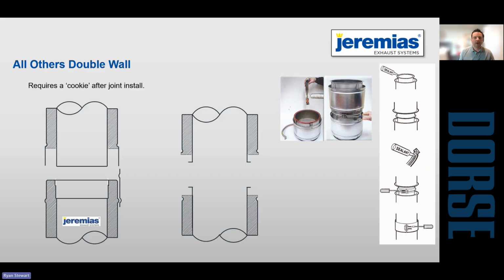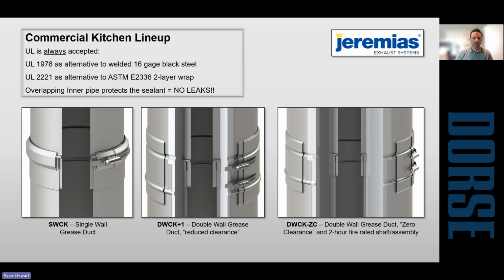The Jeremias product has a UL listing up to negative 20 inches of water column, where the others don't have a listing specific to pressure drop. So here's some different configurations. You can do single wall. That would require it either be exposed and 18-inch clear from combustibles, or you'd have to double fire wrap it. Then they offer a double wall product that's reduced clearance.